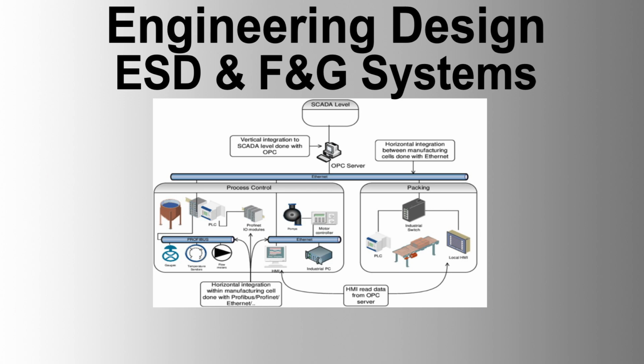3. System components. Processors, dual redundant, capable of executing control functions and cross-checking outputs. I/O modules, galvanically isolated, supporting both analog and discrete signals with diagnostic indicators. Power supplies, redundant 24-volt DC, capable of supporting all connected devices in future expansions. Memory, non-volatile, capable of storing system and application software with sufficient capacity for future configuration. Communication, dual redundant serial links for interfacing with DCS and other systems.